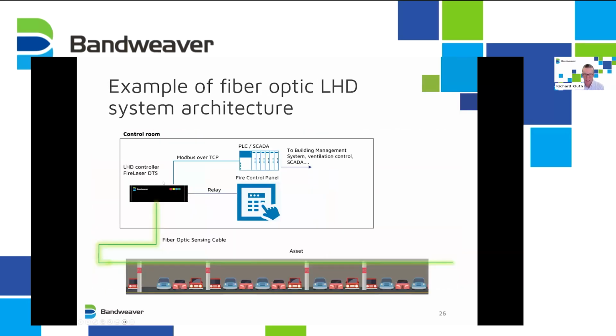The typical setup of the system is normally connected to the fire control panel via relays, and then in some cases Modbus over TCP or Modbus RTU to a PLC or SCADA, where it may be connected to building management systems, ventilation control, etc. And we'll see in some of the examples where that's the case.